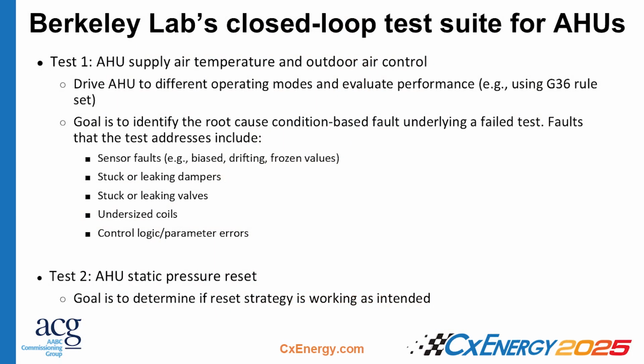So once again, each mode has its own set of pass-fail criteria for determining whether or not a test passed or failed. If it failed, you have additional follow-up functional tests you can do to then drive down the possibilities as to why that test failed. So yeah, this is once again the example of the supply air temperature and outdoor air control. The second test, which is the AHU static pressure reset, we'll talk a little more about in the Guideline 36 section.